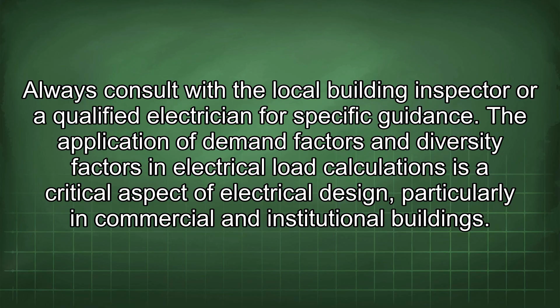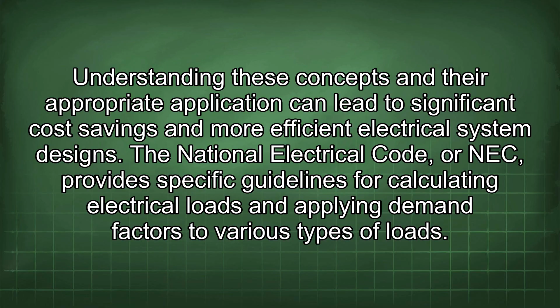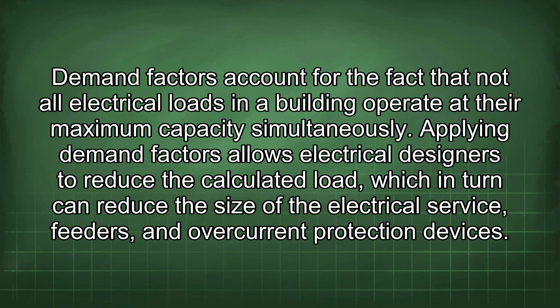The application of demand factors and diversity factors in electrical load calculations is a critical aspect of electrical design, particularly in commercial and institutional buildings. Understanding these concepts and their appropriate application can lead to significant cost savings and more efficient electrical system designs. The National Electrical Code, or NEC, provides specific guidelines for calculating electrical loads and applying demand factors to various types of loads. Demand factors account for the fact that not all electrical loads in a building operate at their maximum capacity simultaneously. Applying demand factors allows electrical designers to reduce the calculated load, which in turn can reduce the size of the electrical service, feeders, and overcurrent protection devices. This reduction translates to lower material costs, reduced installation costs, and improved energy efficiency.